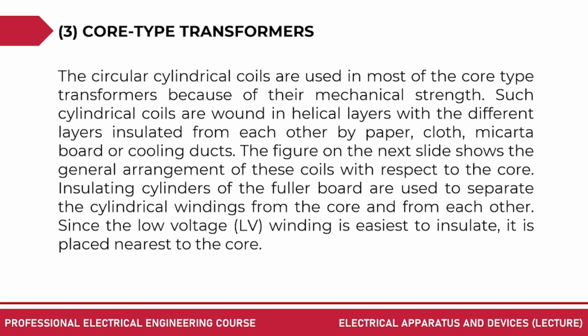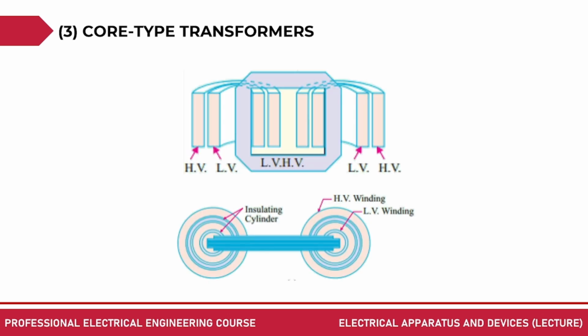The circular cylindrical coils are used in most of the core type transformers because of their mechanical strength. Such cylindrical coils are wound in helical layers with the different layers insulated from each other by paper, cloth, micarta board, or cooling ducts. The figure on the next slide shows the general arrangement of these coils. This is what I'm going to show you with respect to the core. Okay?